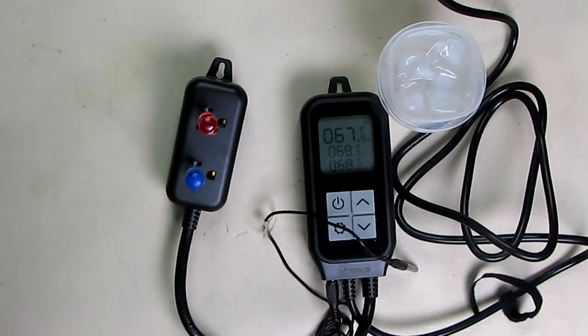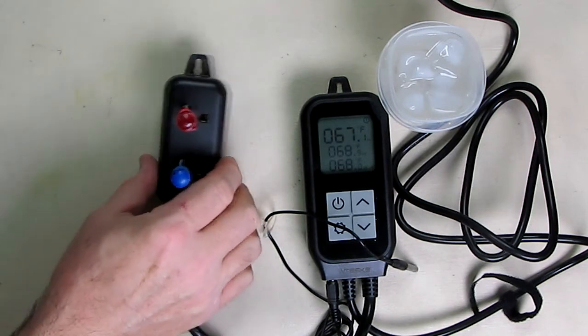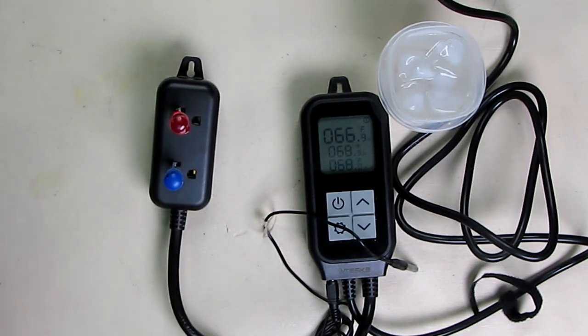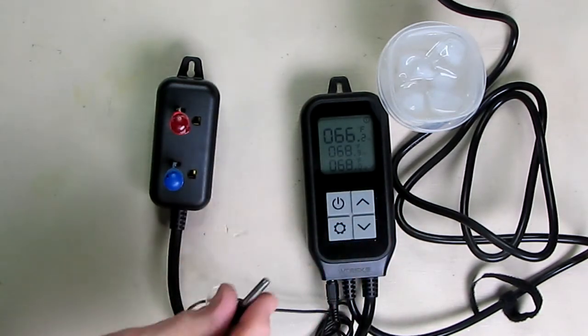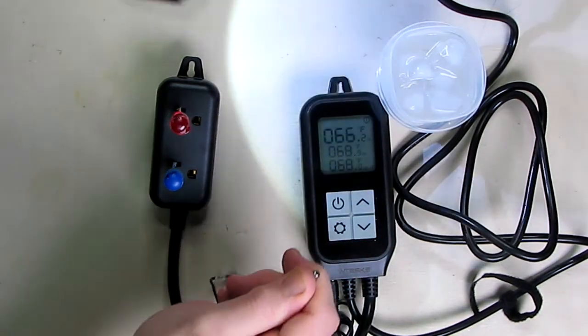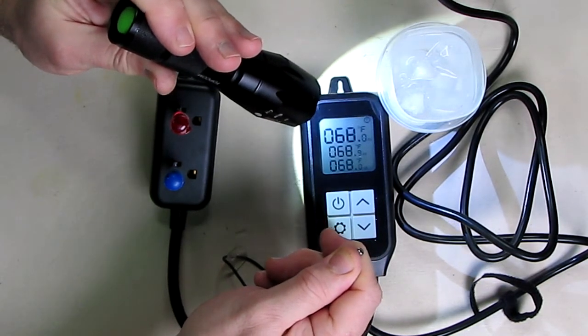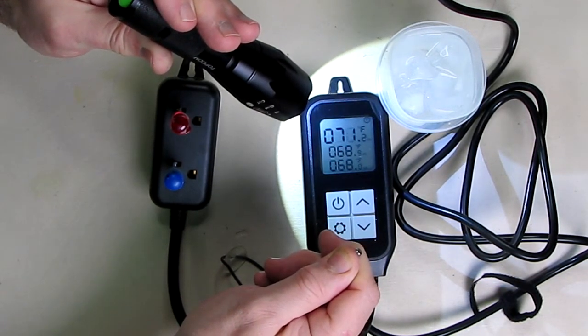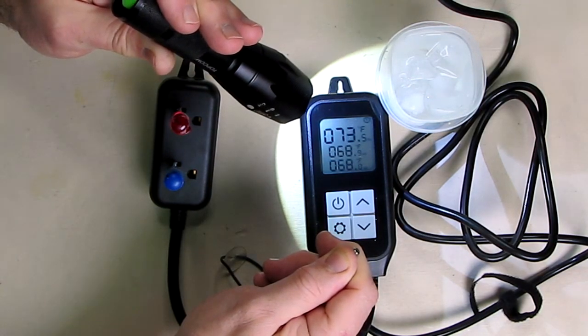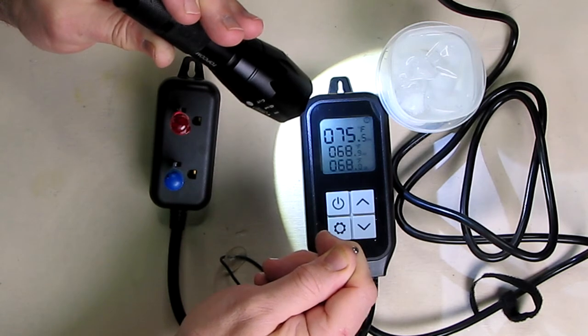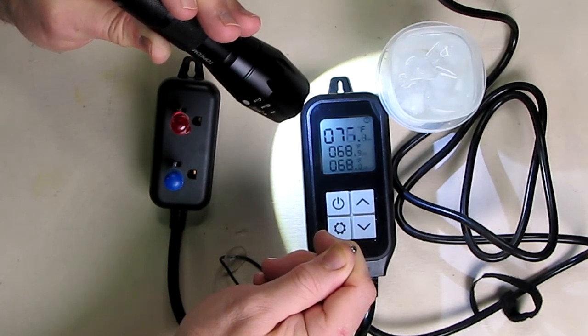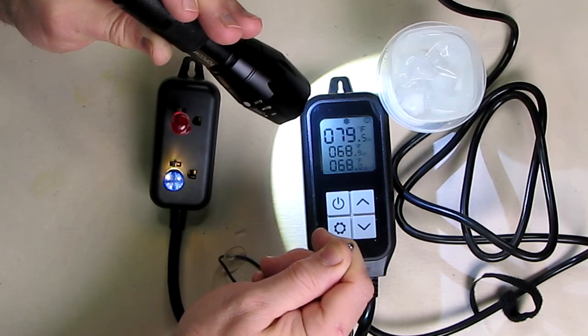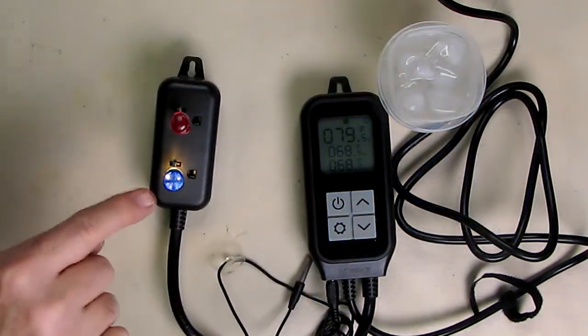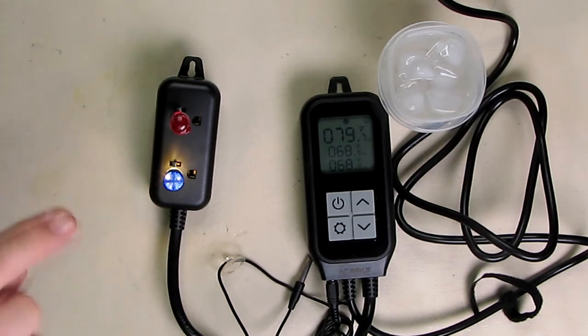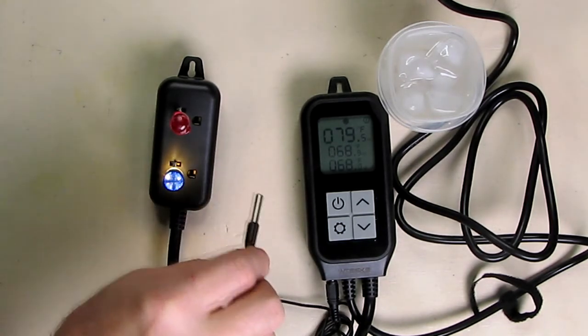So right now, the temperature of the probe is the same as the room temperature right there, pretty much within a couple degrees, and nothing's going to happen. Now let's say that you have this probe, and now the temperature is going to increase. So now I'm touching the probe with my body temperature, and watch what happens. The probe temperature is increasing. So 74, 75, 76, 77, and now the alarm goes off, and you could also see that the cool came on, because now the probe has to be cooled down for this to be happy.